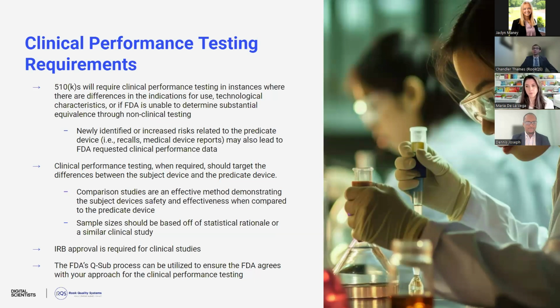So if you're stuck between two predicate devices and aren't sure which one to pick, definitely check the FDA databases for recalls and adverse events, and you would want to pick the one that has hopefully none, but the least amount of those medical device events. So when clinical performance testing is required, it should target the differences between the subject device and the predicate device, particularly for the 510(k) pathway. One thing that we found is very valuable is a comparison study. We find these are effective at demonstrating that the subject device's safety and effectiveness is appropriate when compared to the predicate device. So taking an already existing, cleared, legally marketed device and subjecting it to the same protocol as your device and comparing the results and basically determining that your device is as safe, as effective, if not more, than the predicate device. Sample sizes for these studies should be based off of statistical rationale or a similar clinical study.